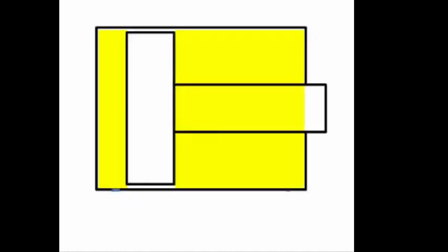In any case, you have some hydraulic fluid on both sides of the piston. But we want the hydraulic fluid to create force on this particular area of the piston so that the piston will be moving forward. Now, what are the chances for the oil to not do the work that is expected of it? Whatever oil is present over here can pass through the gap between the piston and cylinder, and it can go from one side to the other side without doing any kind of work. So that is one kind of leakage.